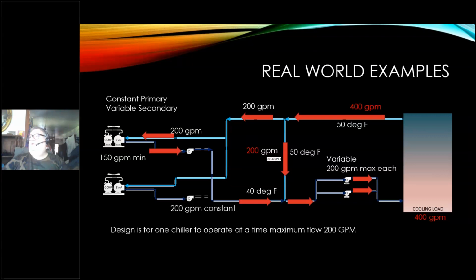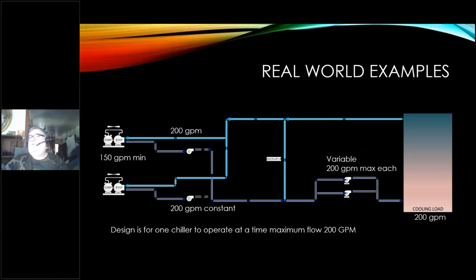50-degree water at 200, 40-degree water at 200 GPM, comes up with like a 45-degree temperature water going into my building. So I'm trying to pump 40-degree water into the building, but I'm getting 45. And then if I maintain the 10 degrees across the building, I get 55 coming back. Eventually, that 55 degrees works its way into the central plant, which makes the second chiller come on, which starts the second pump. We now have 400 GPM in the plant, and it's going all the way through the system, way off the chart. I'm operating full bore for no reason at all, and it's ridiculous.